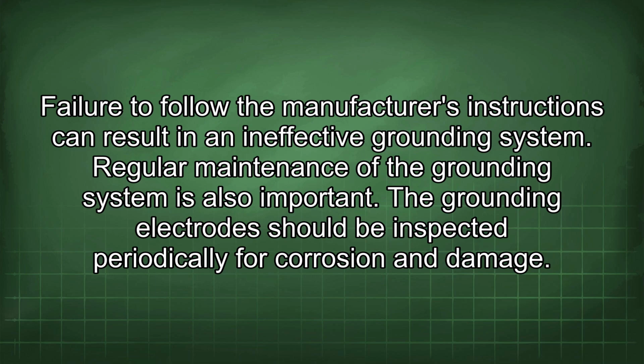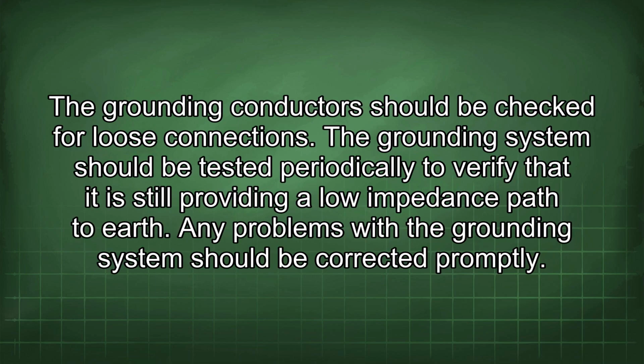Regular maintenance of the grounding system is also important. The grounding electrodes should be inspected periodically for corrosion and damage. The grounding conductors should be checked for loose connections. The grounding system should be tested periodically to verify that it is still providing a low impedance path to earth. Any problems with the grounding system should be corrected promptly.